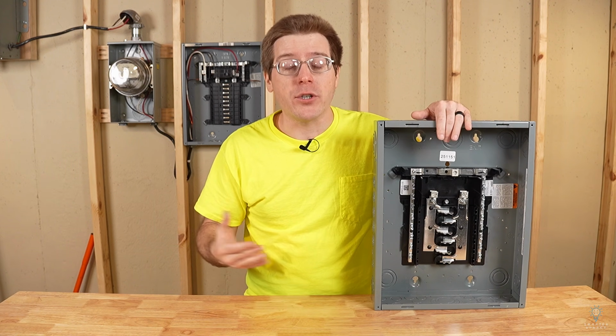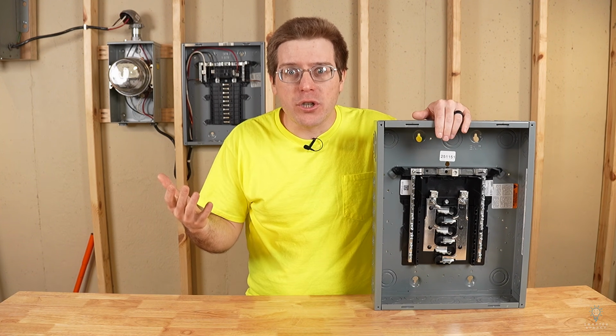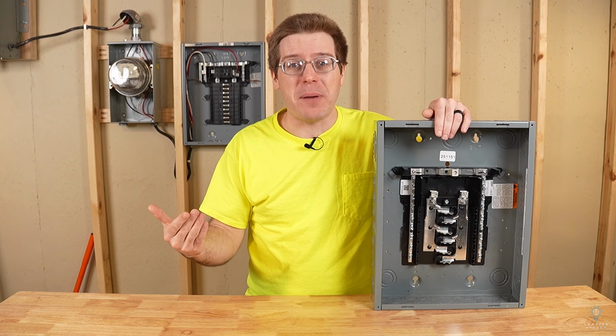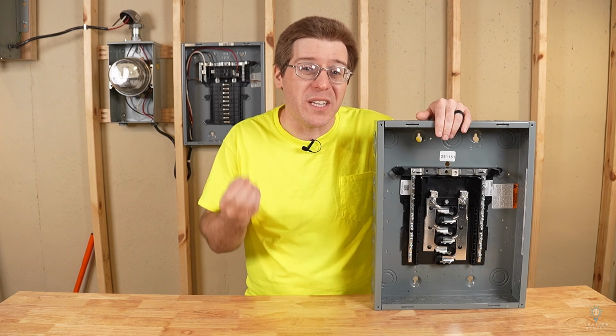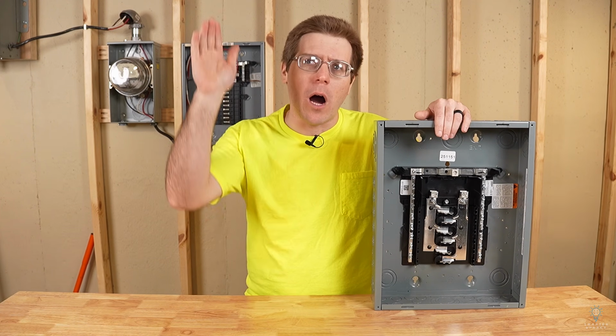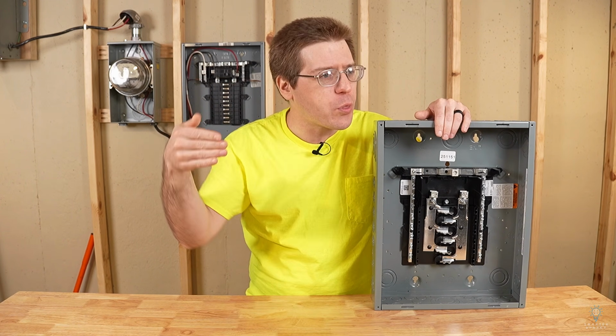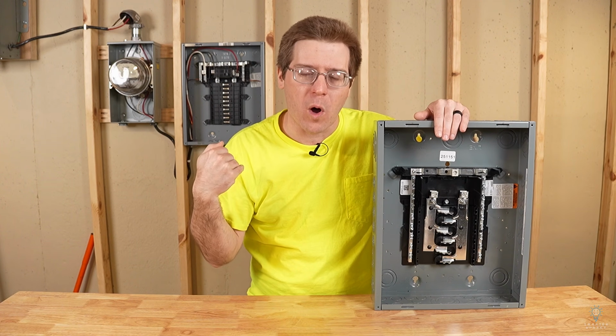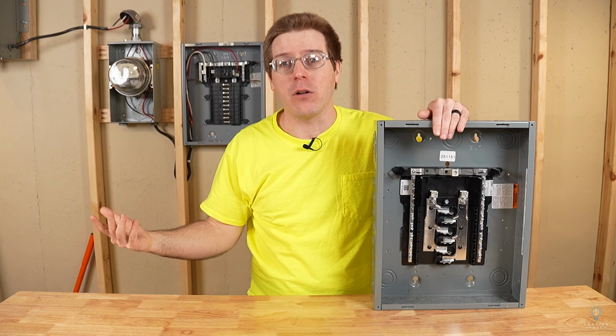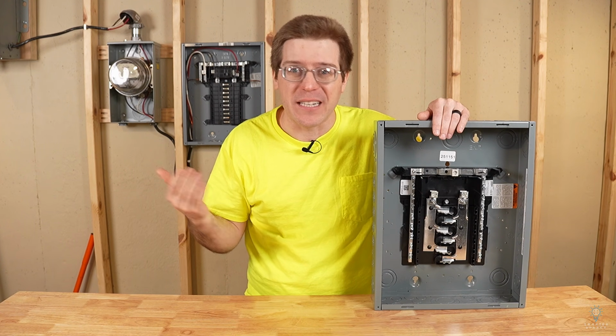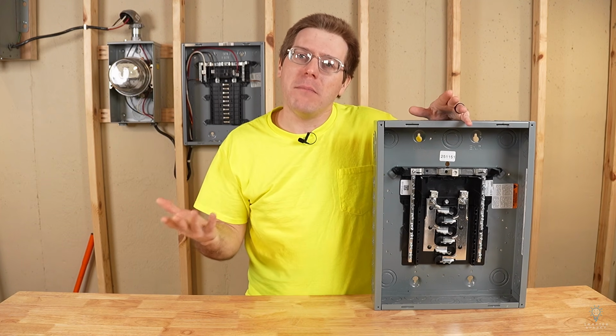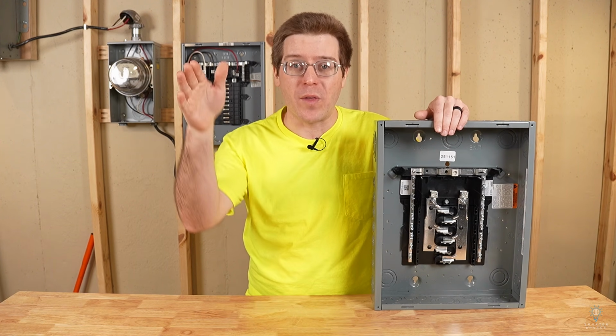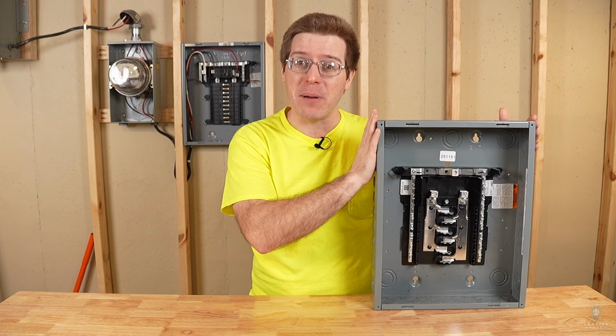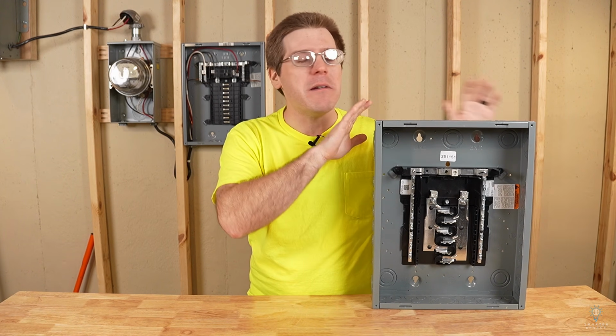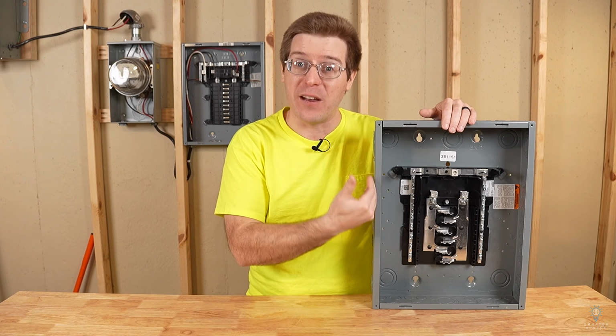Another reason might be that you're doing a remodel on a building. And sure, maybe you could get your circuits to the main panel, but maybe the route to do so is really difficult. Maybe you have to go up through an attic, down a wall, through a crawl space, through another wall, and then there is your main panel. So rather than having to get a whole bunch of circuits through that maze, maybe you just get one feeder wire through that maze, and then you set a subpanel in your remodel area, and then all of your circuits can just get fed from there.